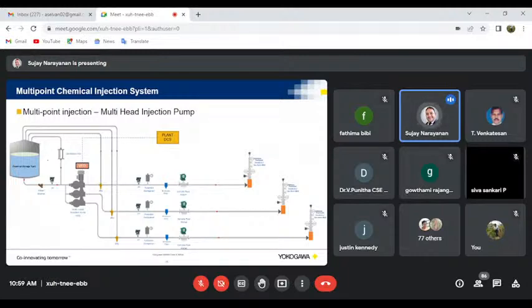You also have cases where a single chemical is injected to 3 injection points or 3 wells. You can see over here, one motor is sufficient, but you need 3 pump heads. And then you can have Coriolis mass flow meters over here, which work on Coriolis technology. Again, we can keep it as a separate subject; it would consume one day if we discussed Coriolis mass flow meters and their working principle. So here the pump discharges the flow, and the operator can see the injection rate currently going to the particular well.